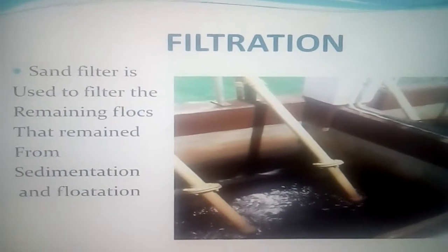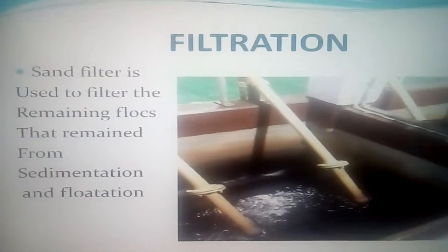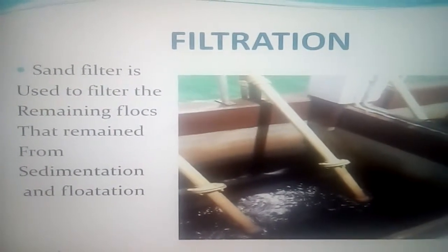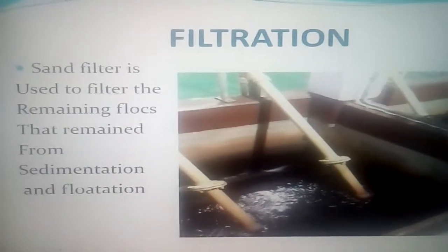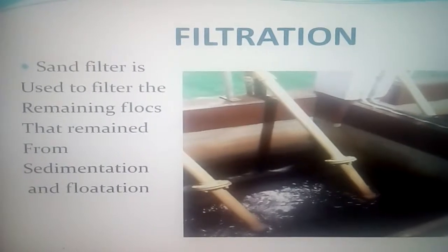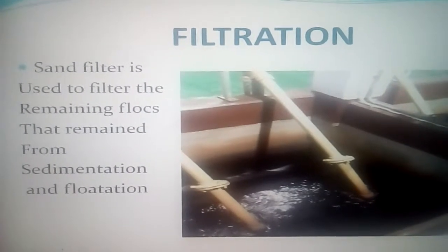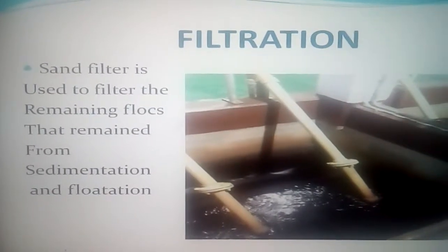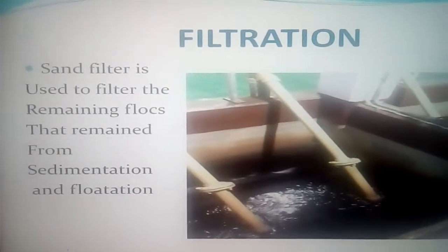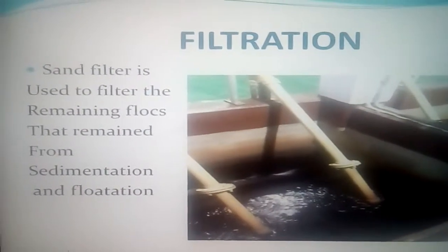So the water is now moving to another stage called filtration. Filtration, here they are using sand to filter all the dirt that is remaining from other stages, namely sedimentation and flotation. So they pour the water over the sand, so the clean water filters through the sand and the dirt remains on the sand.